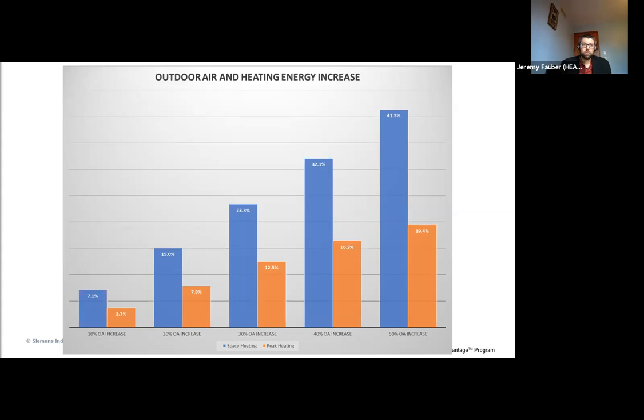And the reason for that is our VAV systems tend to provide less air as you operate at cold temperatures. You just don't need as much air to heat the building. And so your outside air percentage really gets a lot higher when you're in these colder temperatures. It starts out at that 24% on a peak day. As it cools down and my VAV drops to like 75%, now I might have been 30% outside air. When it gets down to 50%, I'm now a 50% outside air unit. So that's why this percentage increase is so much higher.